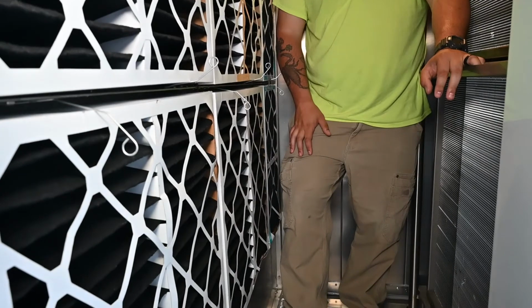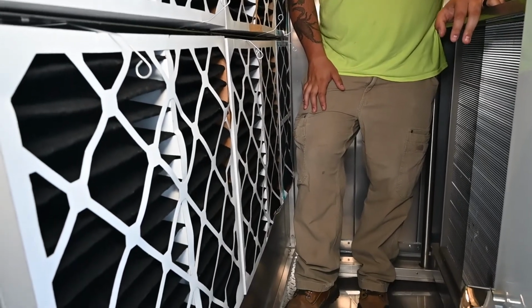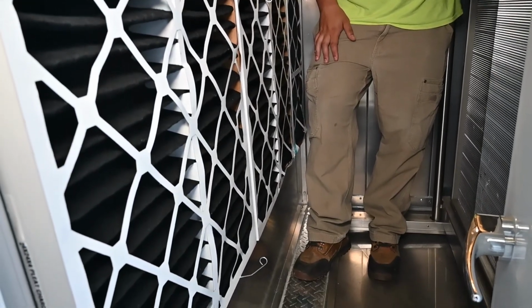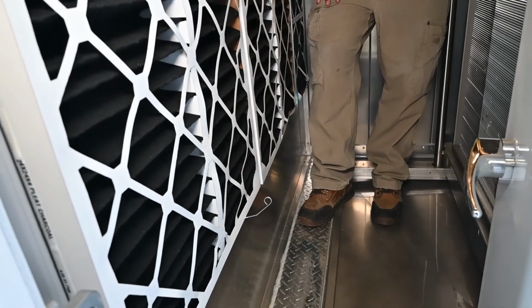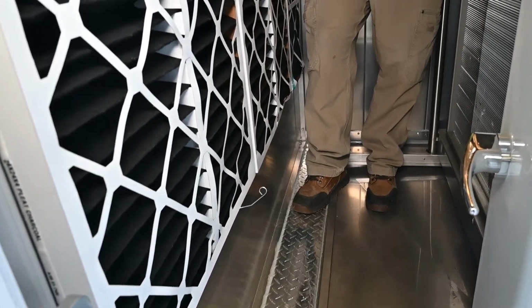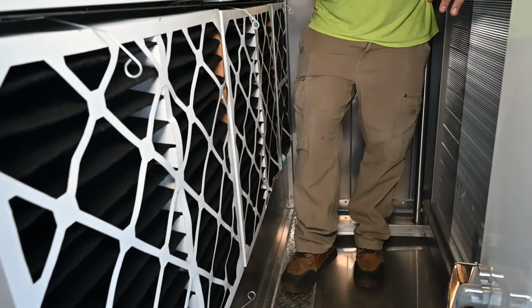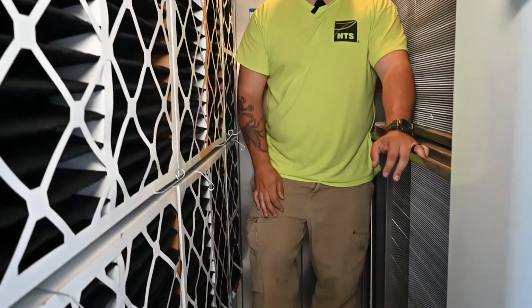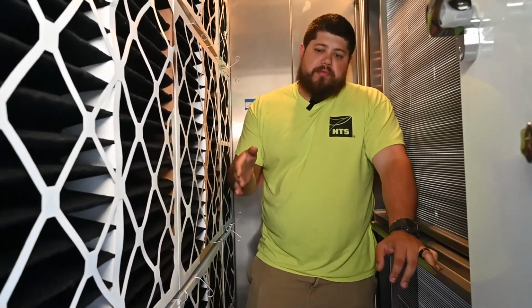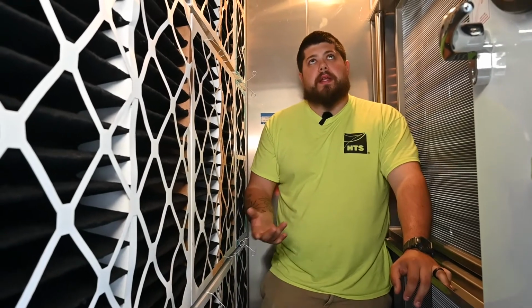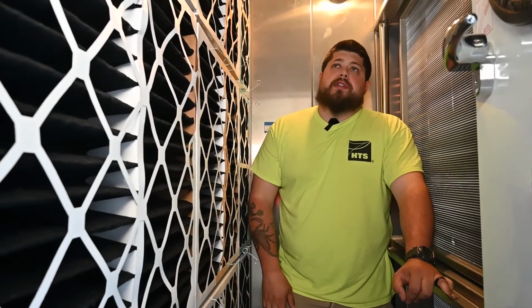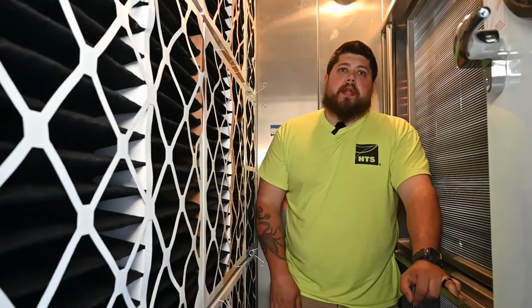My assumption is most people that are going to be working on this unit work in the area, and with that being said, they probably have an understanding of when they should be replaced. There is going to be a Magnehelic right there on the other side of this wall that can be set for a differential pressure of when you see fit to change these filters, whether it be an inch or an inch and a quarter. You can check to see when you need to change it, and that'll do it here.